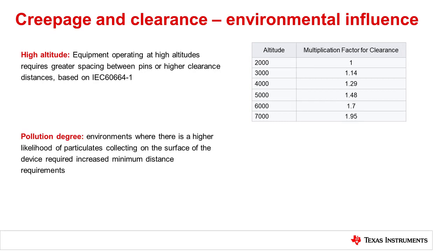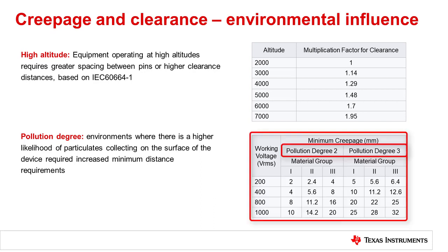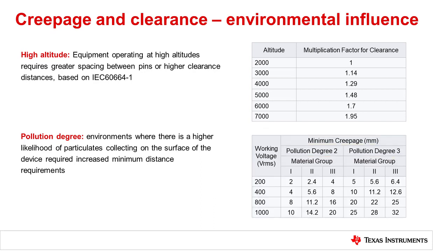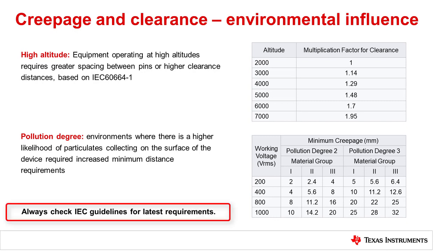Similarly, in operating environments where there is a higher likelihood of particulates collecting on the surface of the device — thereby creating conductive pathways — the consideration of the pollution degree will also influence the minimum distance requirements. Both altitude and pollution levels are rated for the end equipment operating environment from the end equipment standards, so it's wise to always check IEC guidelines for the latest standard.